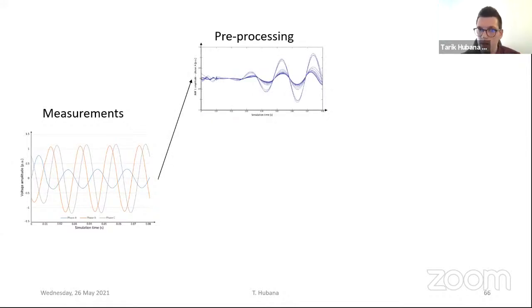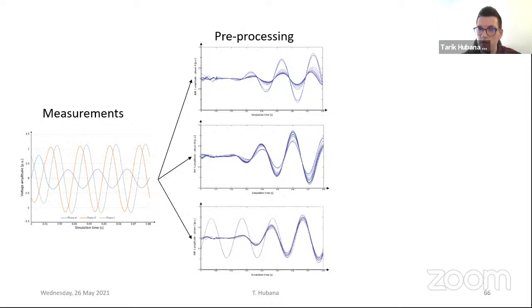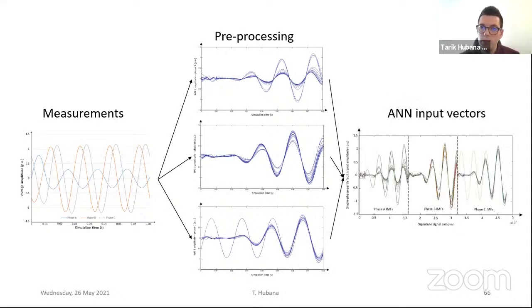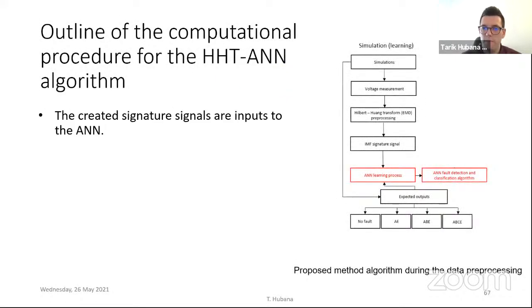So we measured voltages at the bus number 2. We pre-processed these 3-phase voltages with the HHT. We coupled them together into one ANN input vector in order to create the signature vector for each fault scenario, and then we trained our network. The network training was done according to the algorithm shown in the right-hand side. So we did some simulations, we measured voltages, we pre-processed these voltages, we obtained IMFs, we created the signal. After that, the learning process of the neural network was initiated with expected outputs for 3 types of faults and no fault. And we had our fault detection and classification algorithm ready.